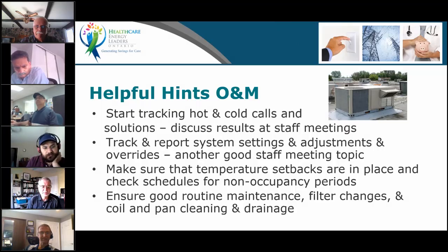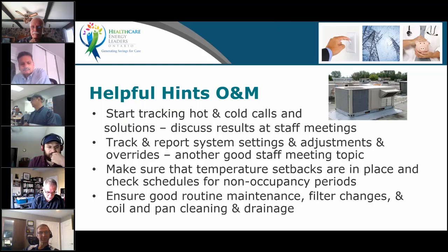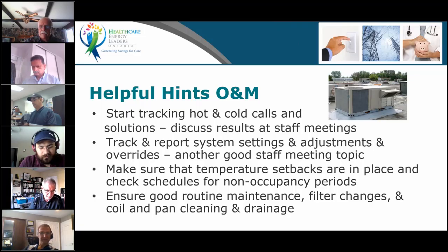Because right now we talked about the ventilation units, which are the main air handler. But when we talk about ventilation, we also have to talk about the diffusers, how the air gets into the space. And when we're talking about hot and cold calls, those diffusers often become really the problematic system. The operator may just go there and do some adjustments, but the problem is elsewhere. Maybe the diffuser is not well aligned, it's against a wall, and the air is just dropping down that wall. And then the operator says, oh, that person's always complaining, I can never satisfy them. That is possible, but it's also possible that it's due to the distribution of the air.